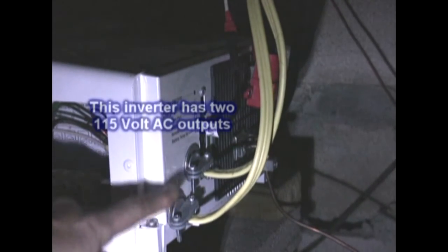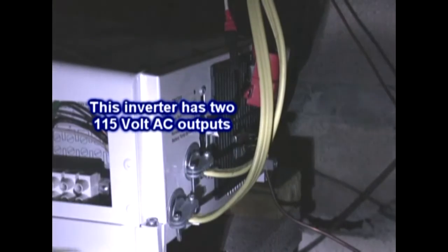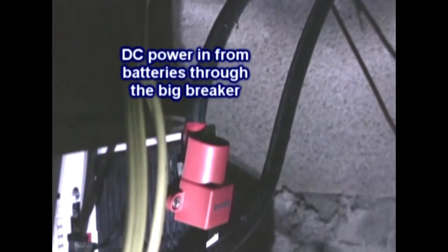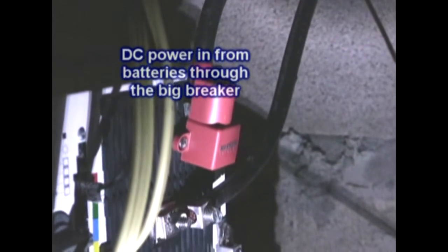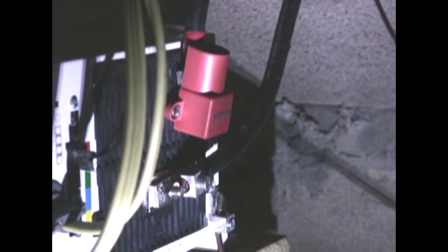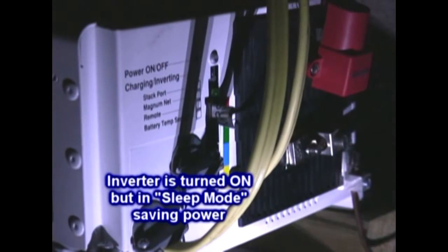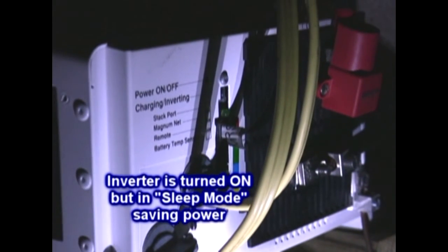And you can see that it has strain reliefs just like our other boxes and equipment. And this is the power going out. Our power coming in comes in 2 large wires. You can see our plus and minus from the battery bank comes into the back of the inverter, and the red cap is over the hot wire there, the plus wire, and then we've got the ground wire as well. And you can see it's blinking because it's in sleep mode right now, waiting for a load to come on, waiting for somebody to use some electricity. Everything is well marked on there.